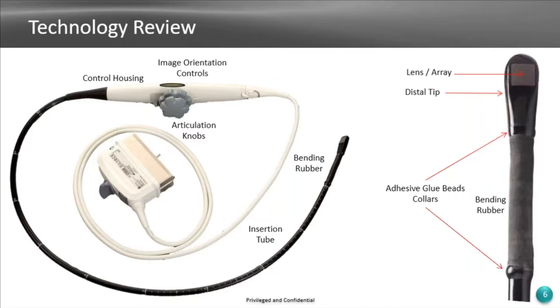This particular device here is a GE6VT-D. We go into the GE user manual, and GE has a matrix saying you can use all these different chemicals—it could be 30 different chemicals—to clean and disinfect these probes and devices like Trophon and things like that. So we take samples of our materials, whether it's a bending rubber, glue, a lens seal, or the lens itself, and we submerge that in those chemicals for an extended period. We call it accelerated chemical testing.